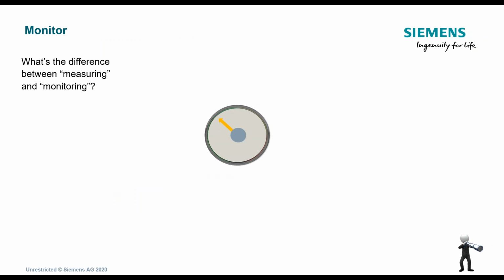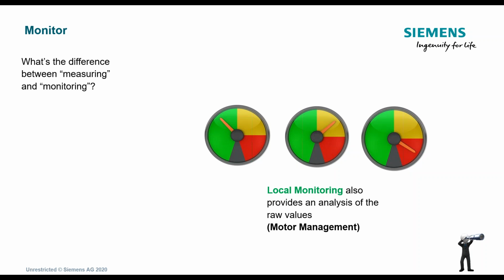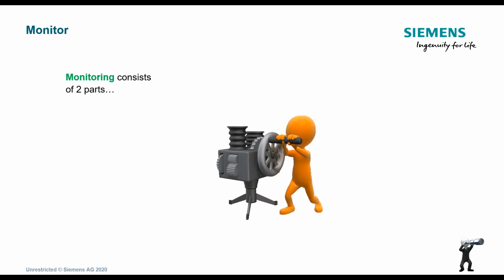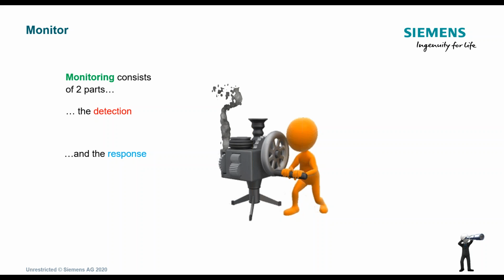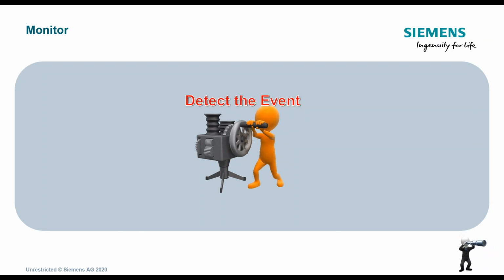All right, now let's move on to monitoring. What's the difference between measuring and monitoring? Local measuring only provides raw data. But if we're monitoring, then it provides analysis of that data. And that is where it separates and comes into a motor management system. Okay, so monitoring consists of 2 parts, the detection and the response. And that's where I was saying that the local remote, or the SIMOCODE, is doing the detection, it's continuing to monitor, but then it sends the alarms or situations to the controller and says, how do you want me to respond? And that's where the PLC or the controller becomes, again, an alarm handler and a traffic cop.